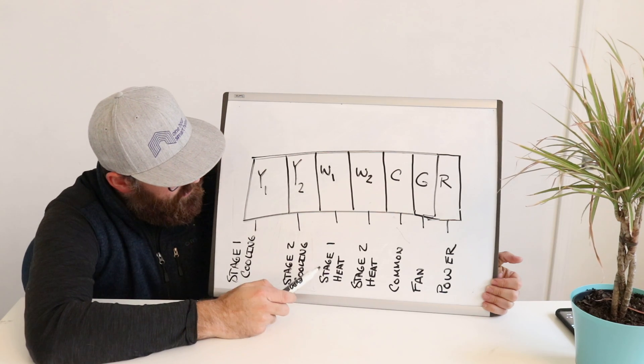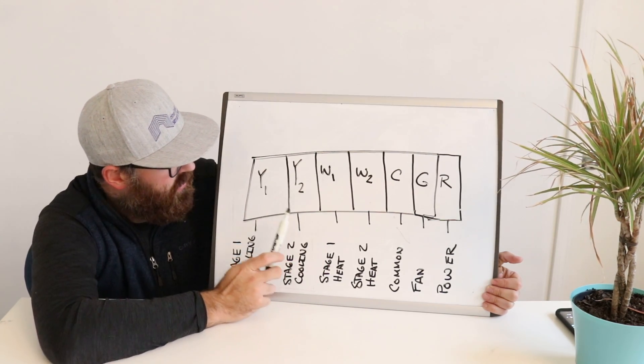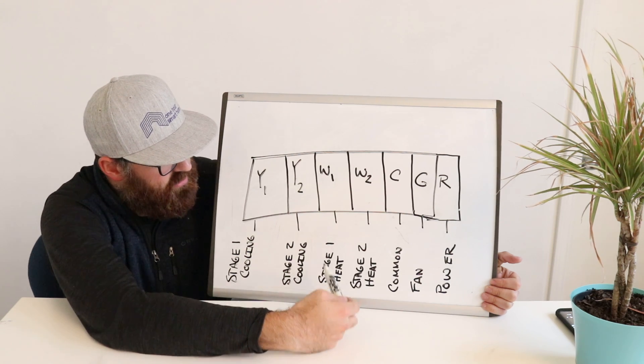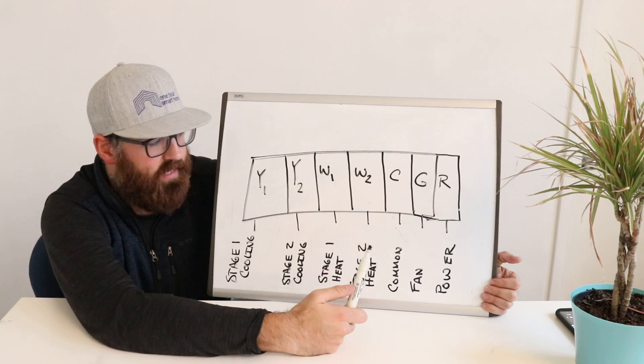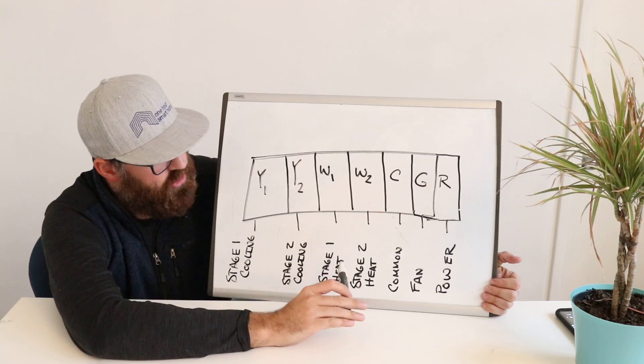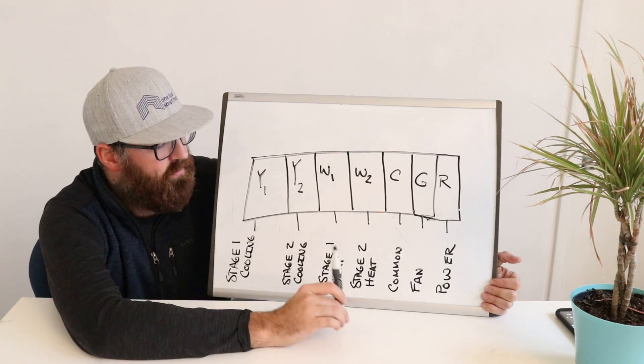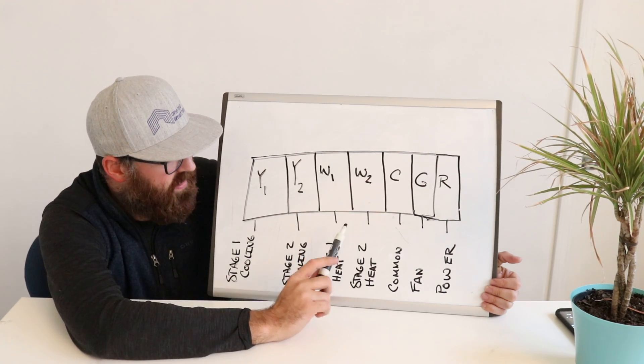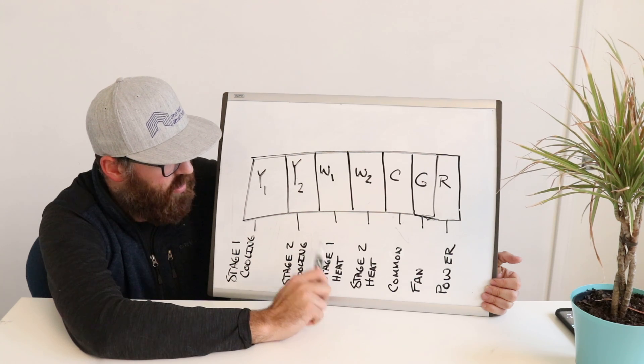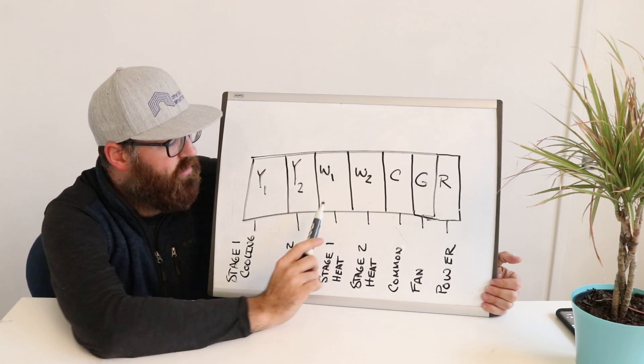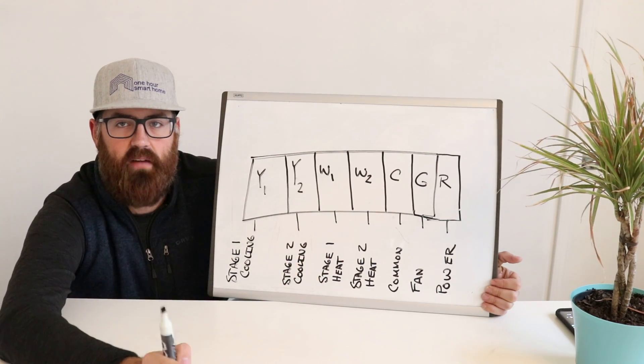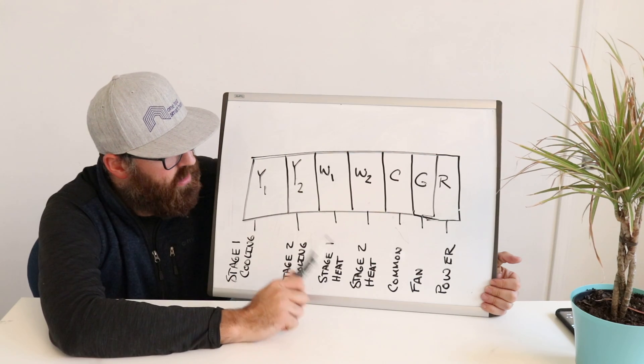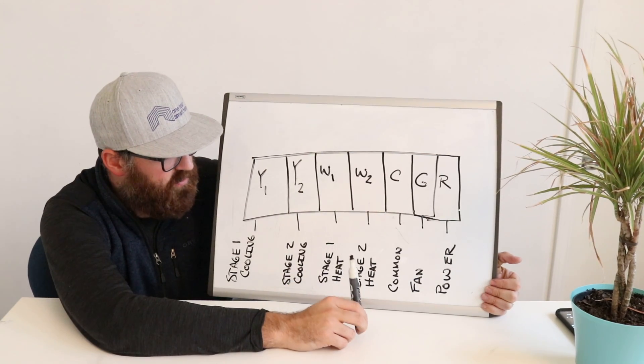So now we're on to the W's. Y is cooling. W is heat. Now the same concept applies for W1 and W2. W1 is stage 1 heat, so that's a low heat setting, the most energy efficient. Now when you're calling for a lot of heat, your thermostat really needs to ramp it up with the amount of heat that you're providing on a cold day. Then it's going to call for stage 2 heat, and that's what your W2 wire is. So you may have a W1 wire and a W2 wire, or you could just have a W1 wire or a W wire, which means you just have one stage heat. But if you've got two of these wires, a W1 and a W2, it means that you've got stage 2 heat. Just means more flexibility for heating and cooling.